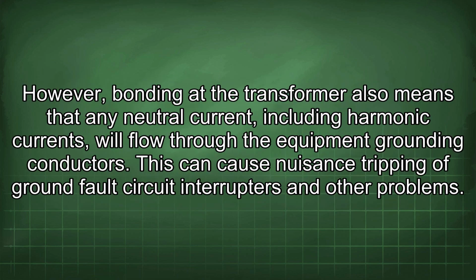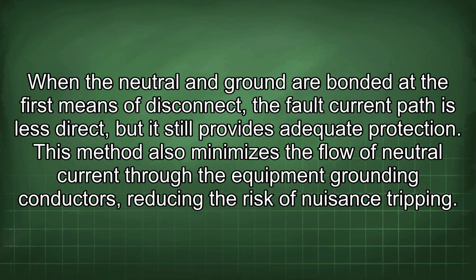However, bonding at the transformer also means that any neutral current, including harmonic currents, will flow through the equipment grounding conductors. This can cause nuisance tripping of ground fault circuit interrupters and other problems. When the neutral and ground are bonded at the first means of disconnect, the fault current path is less direct, but it still provides adequate protection. This method also minimizes the flow of neutral current through the equipment grounding conductors, reducing the risk of nuisance tripping.